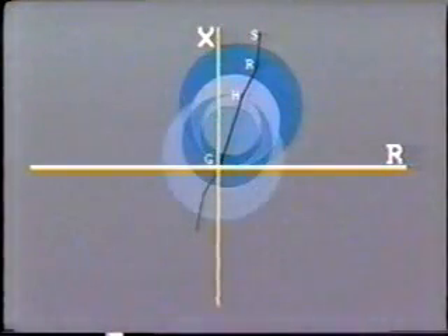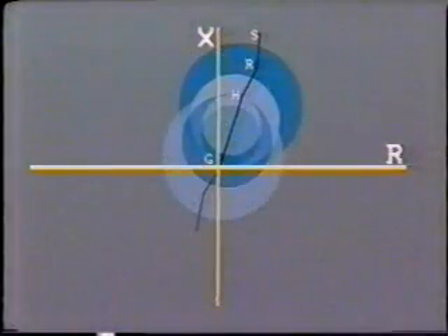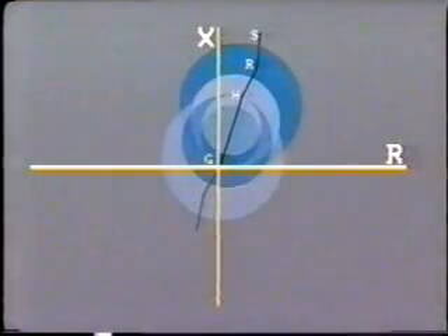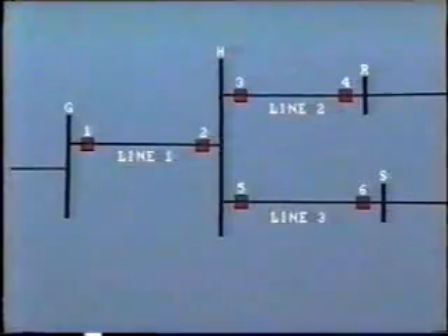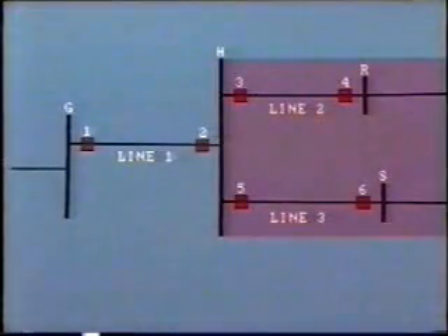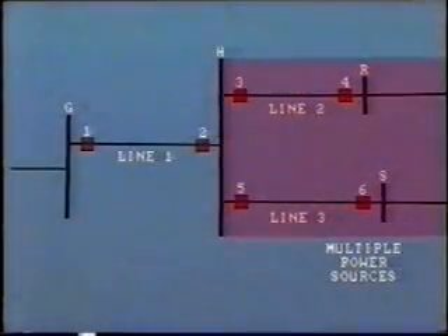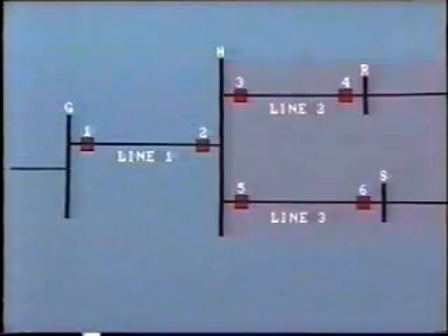We can superimpose the circle diagram for the distance relay which is installed at bus H to operate breaker 2. All of these diagrams are included in your workbook so that you may give more time to study them in detail. Unfortunately, most of our high voltage protection is not that easy because the system is more complex. For example, it is probable that at bus H there will be additional transmission lines connected, some of which may be connected to other power sources.